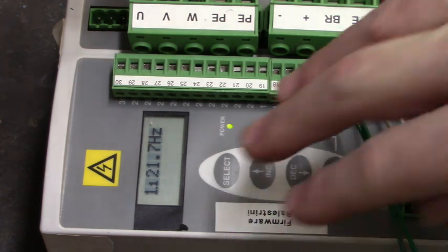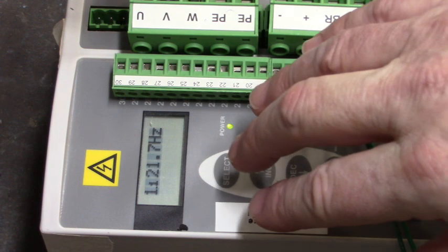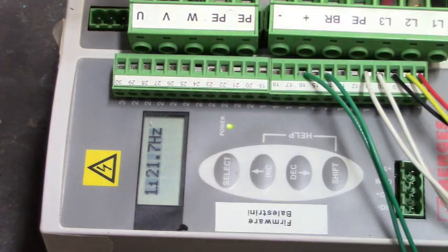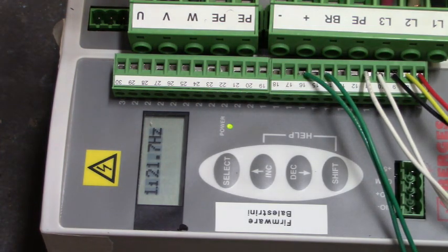The problem with this drive is the power supply would drop out every now and then. And so I replaced some capacitors on the switch mode power supply circuitry. Those capacitors, they'll get us every time.